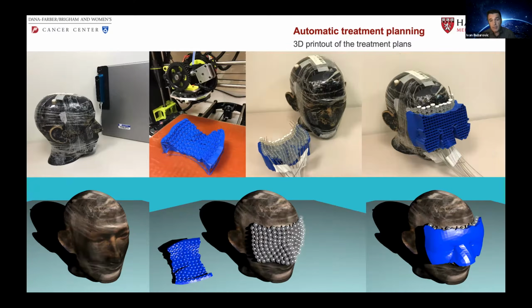So what is the additional benefit? We print out our applicator holder in a way that allows for backscatter. Because we know that we deliver a cold plan because of the lack of backscatter, this applicator holder will solve another problem: accurate delivery of the dose. Treatment planning systems, excluding model-based treatment planning systems, for instance ACE or Acuros, will not show this difference, and of course other measurements show it. It is also known that we deliver a colder plan in the presence of bone on a scalp, and when we treat the flank, because of the proximity of the lungs, we deliver up to a 4% hotter plan.